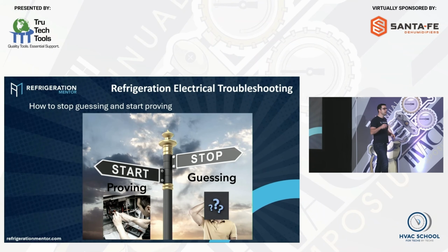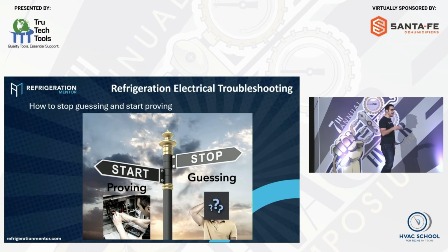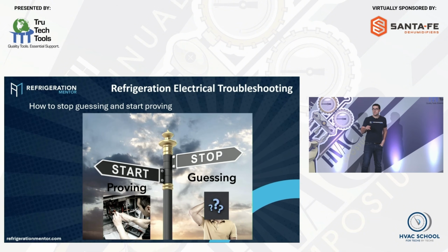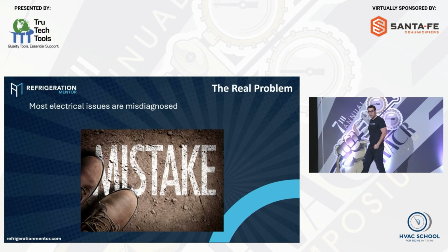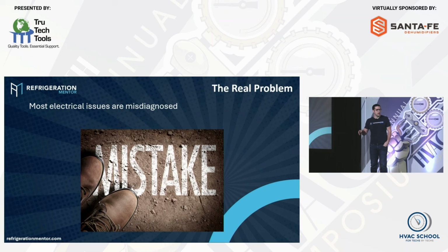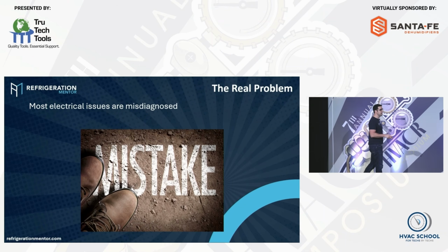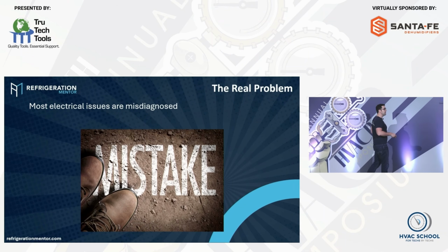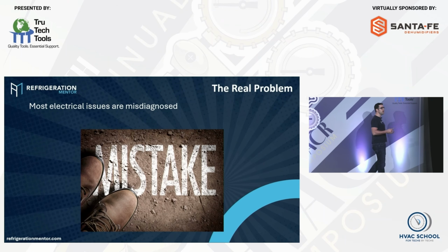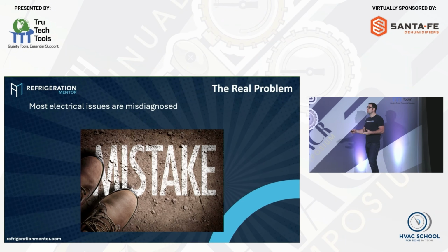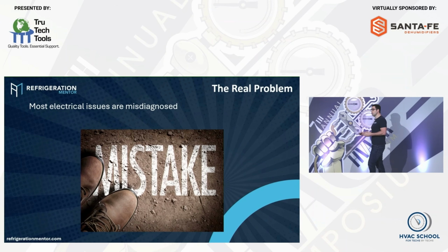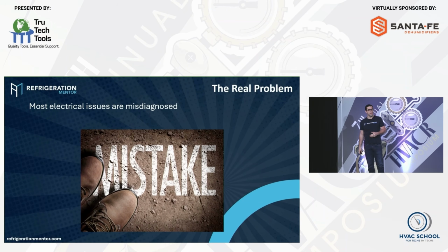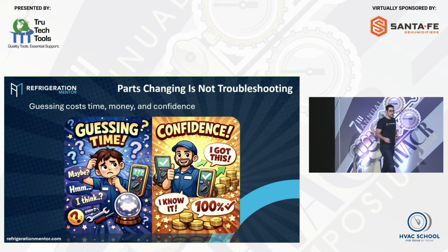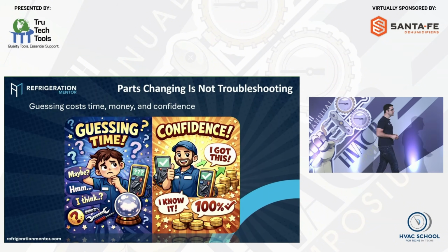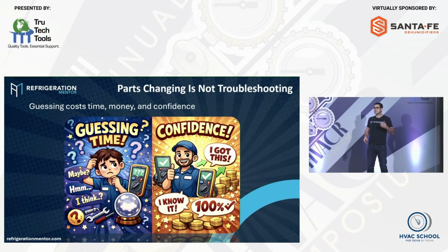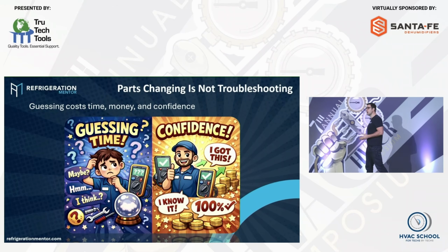Okay, refrigeration, electrical troubleshooting, how to stop guessing and start proving. This is so important. You got to prove your stuff. The real problem is a lot of electrical failures are misdiagnosed, because one of the things that I've seen over and over again is the proving method. We got to prove that there's something wrong, something has failed. Parts changing is not troubleshooting. Guessing costs time, it costs money, and it costs confidence.